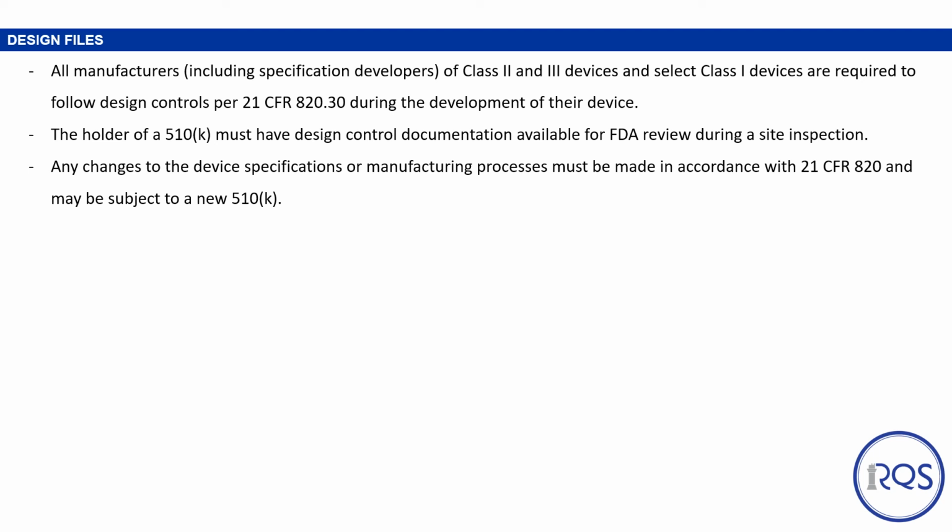All manufacturers of Class 2 and 3 devices and select Class 1 devices are required to follow the design controls per Part 820.30. The holder of a 510(k) must have design control documentation available for the FDA during a site inspection. Any changes to the device specifications or manufacturing processes must be made in accordance with Part 820 and may be subject to a new 510(k).